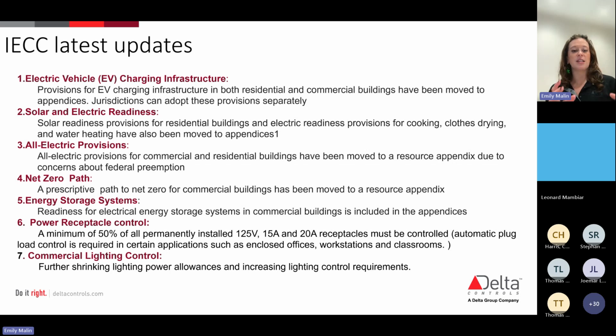When we look at what's changed in 2024 specifically for our industry, the biggest thing is power receptacle control. It's a significant change: automatic plug load control is now required in certain applications such as offices, workstations, and classrooms. A minimum of 50% of all permanently installed 120 volt, 15 amp receptacles must be controlled. This is a pretty big difference from what we've seen in the past, focusing on controlling more of our energy usage.